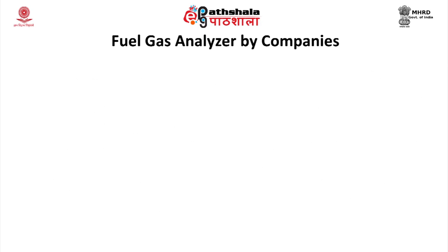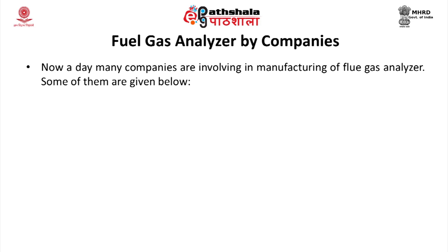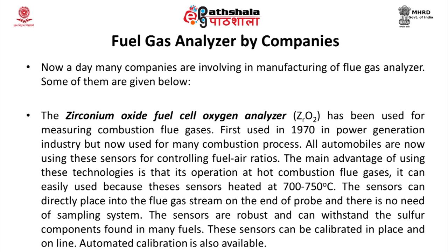Many companies are involved in the manufacturing of flue gas analyzers. The zirconium oxide fuel cell oxygen analyzer is used for measuring combustion flue gases. First used in 1970 in power station industries, it is now used in many combustion processes, and all modern automobiles use this sensor for controlling the fuel-air ratio. It operates with hot combustion flue gases, is heated at 700–750°C, is robust enough to withstand sulfur components, and can be calibrated in-place and online, with automated calibration also available.